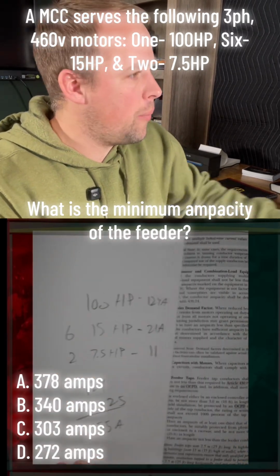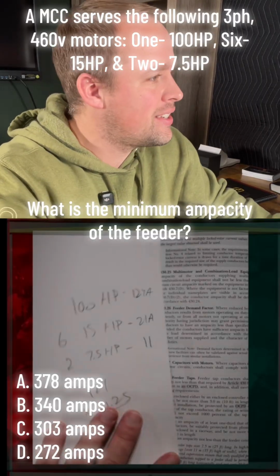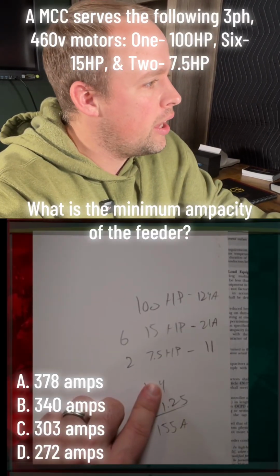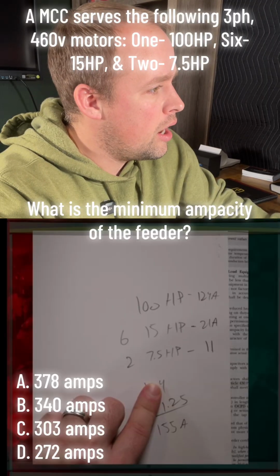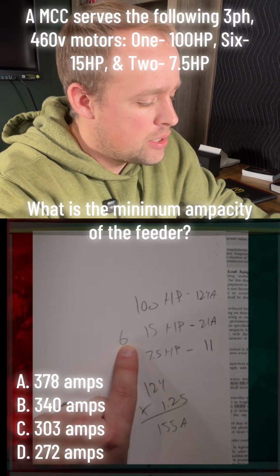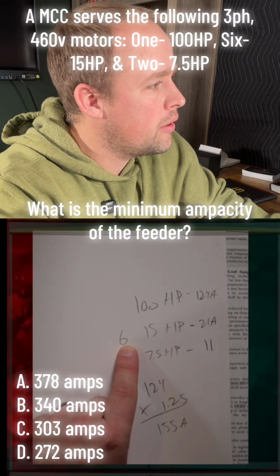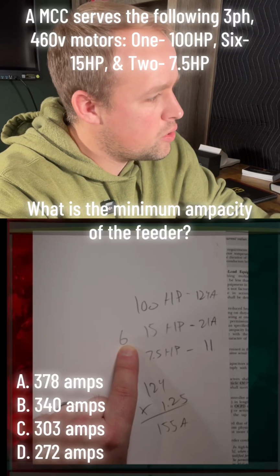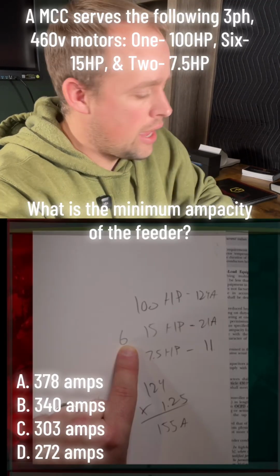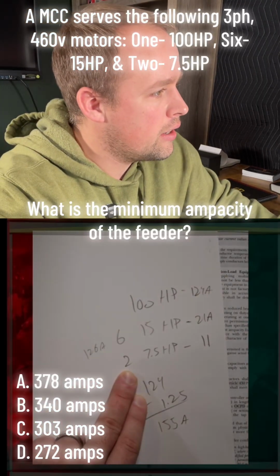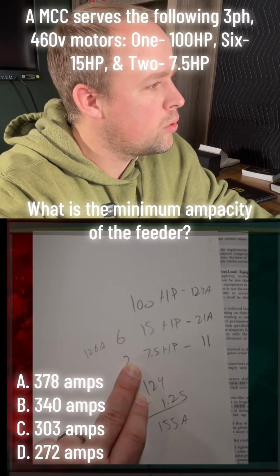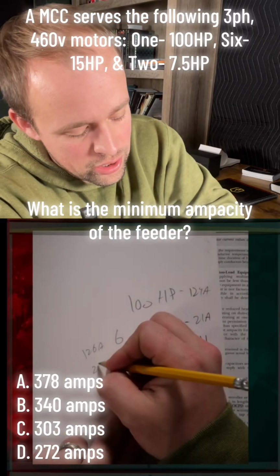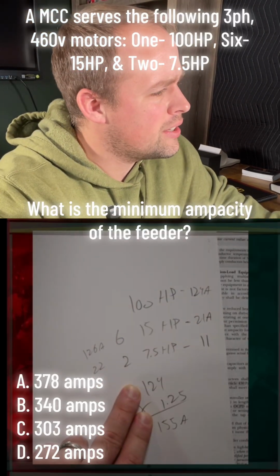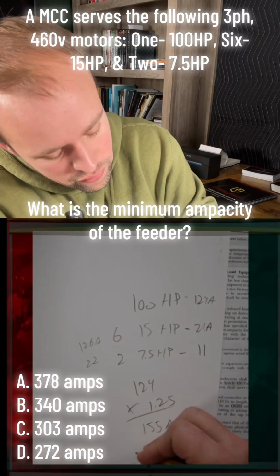So 6 times 21 is in total 126 amps, and then 2 times 11 is 22. 126 plus 22 gives me 148.